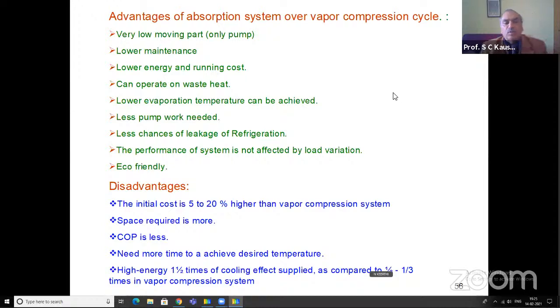For solar cooling systems, vapor absorption systems operated with solar energy is the best option. But still we may have drawbacks, like initial cost becomes 15 to 20% higher because of the solar operation, and space requirement is also more, COP is less, and it needs more time to achieve a desired temperature. High energy is needed, nearly 1.5 times more for the cooling effect supplied, as compared to 1.2 to 1.3 times for the vapor compression. So these are the vapor absorption systems.